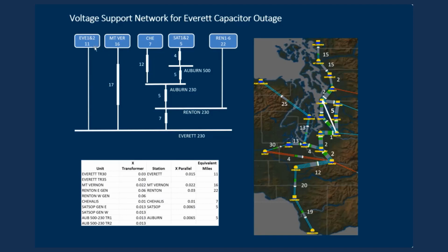We now look at the distance between that generator, the high side of the generator transformer, and the bus which has the shunt capacitor. For Everett, the distance is 0 because the capacitor is located right at the Everett generating station. For Mount Vernon, the distance is 17 because to get from Mount Vernon, we have to go to Marysville, which is 15, and then to Everett, which is 2. So that's a combination of 17 miles to go from Mount Vernon to Everett. For Chehalis, we have to go 12 miles to Auburn.